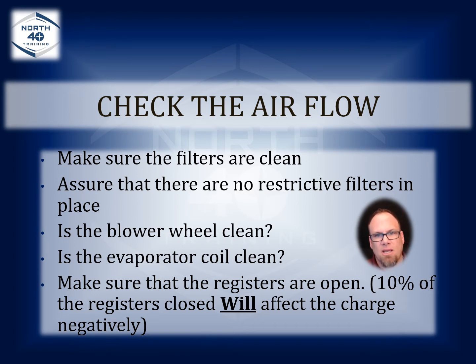Well, that's a loaded question. That's a tough one. It depends on the type of blower. Now, if you've got a multi-speed blower, the multi-speed blower doesn't know that you've closed all those registers. It's still trying to push down those runs. And just because you close off those registers doesn't mean the airflow is automatically going to go to a different run, say to the second floor or to the weird bedroom above the closet or to the new addition that you've put in that never had good airflow. It just doesn't work that way.